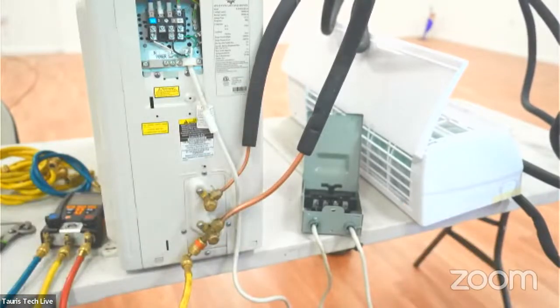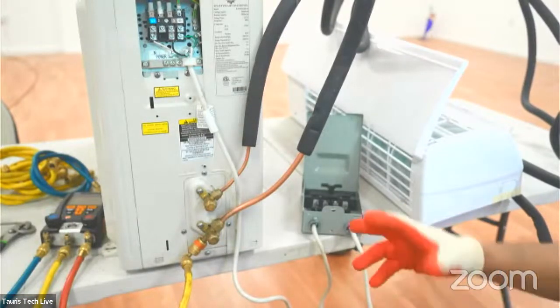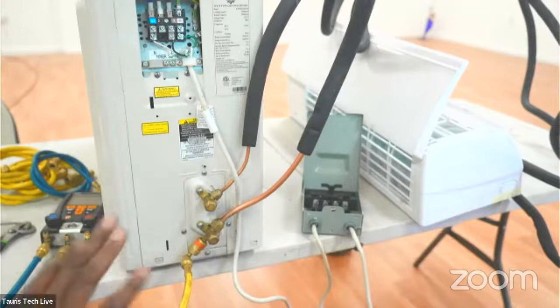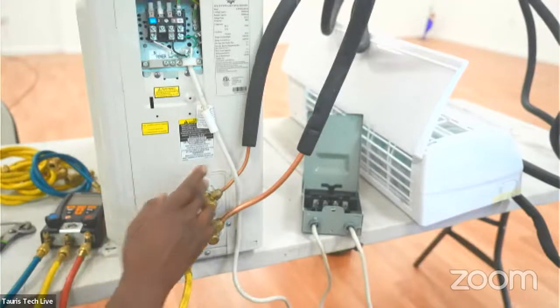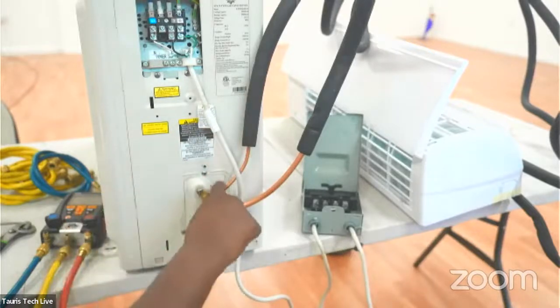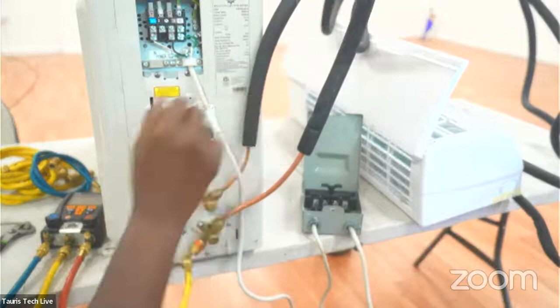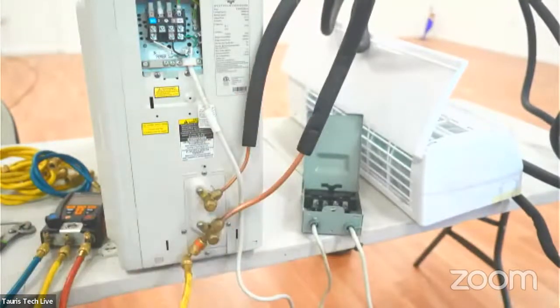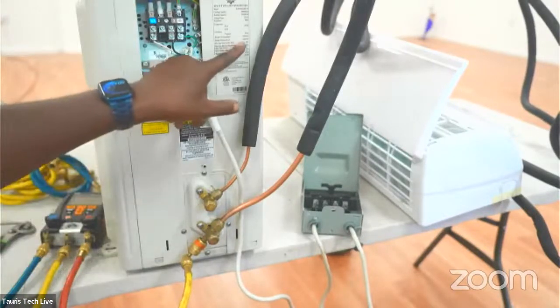Both insulated. Yes. But how does it transfer? The four-way valve. The four-way valve switches between sending liquid that way or sending vapor. So in cooling mode, high pressure liquid goes out. But in heating mode, we're sending high pressure vapor out. We'll draw it out and talk about it, but that's why we have the different test pressures.